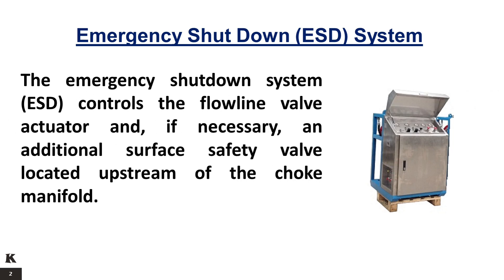The Emergency Shutdown System ESD controls the flowline valve actuator and, if necessary, an additional surface safety valve located upstream of the choke manifold. Additional push-button stations can be located, for example, at the steam heat exchanger, separator, gauge tank, and burner pedestals. The ESD system can be complemented by high or low-level alarms.